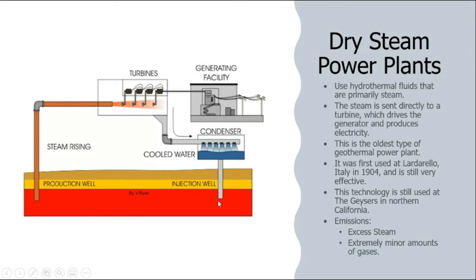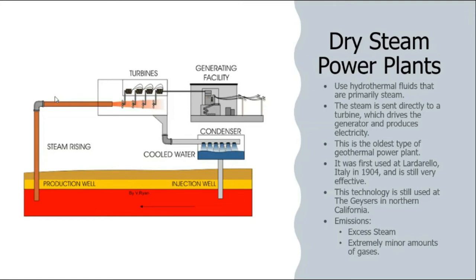The steam is condensed in cold water in a closed loop. However, there are harmful gases present — such as hydrogen sulfide, carbon dioxide, and methane — which can cause global warming impacts. Other gases like hydrogen sulfide cause corrosion. So this system requires regular maintenance, and that is a problem with dry steam power plants.